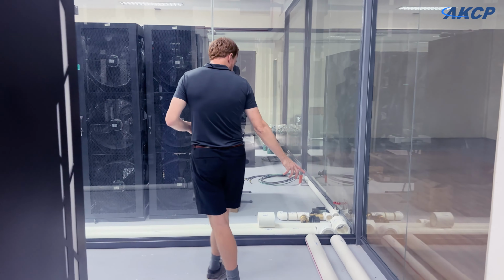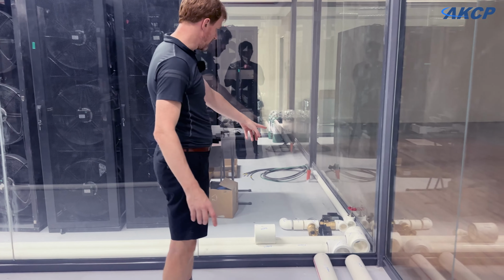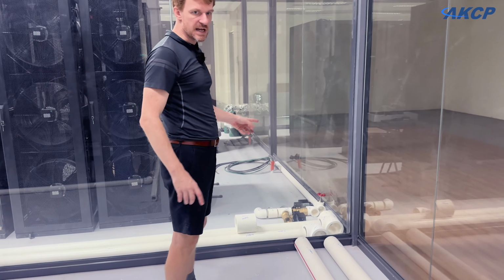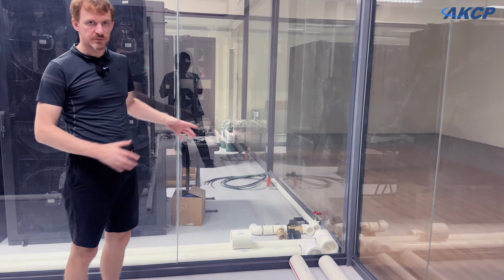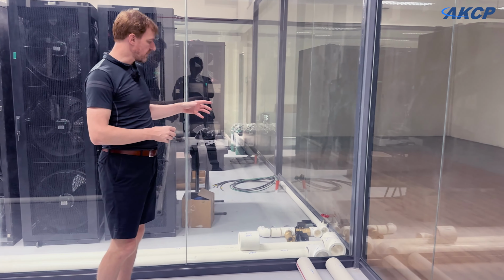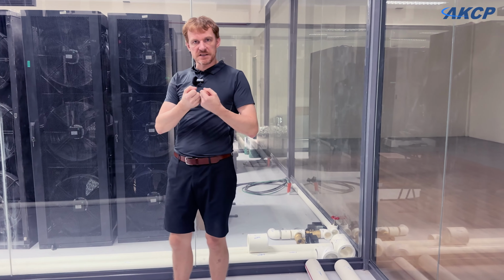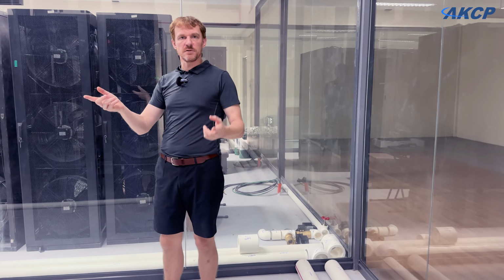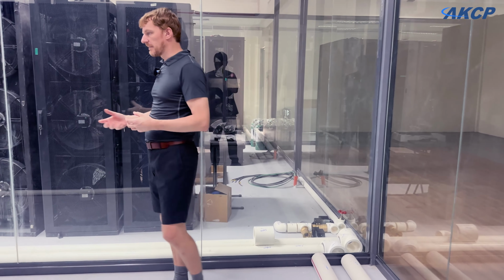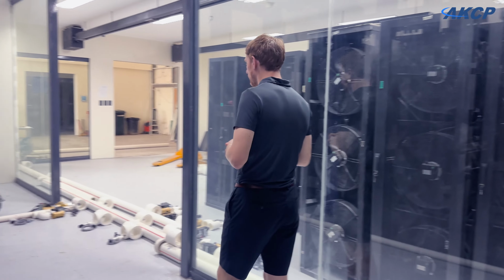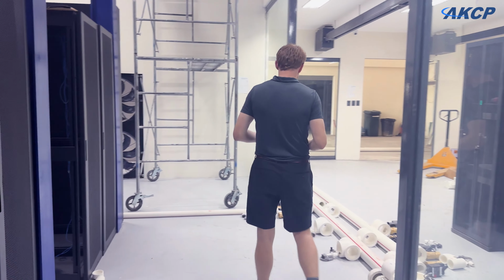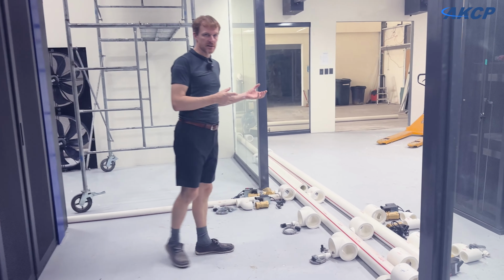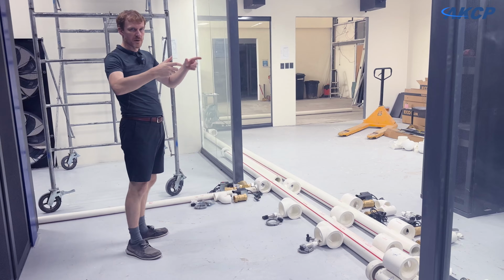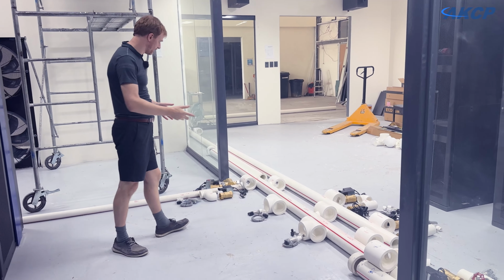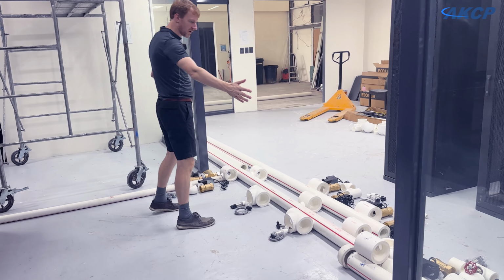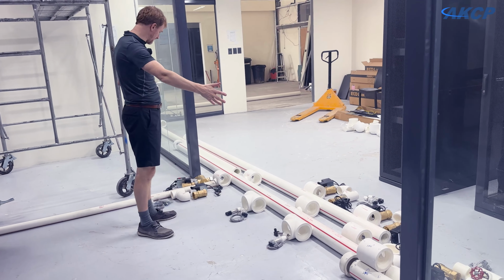Along the way, from the 4-inch main loop, we have 2-inch tap-offs which take the water out to the individual containment pods, and from those 2-inch tap-offs we split into 1-inch lines which go to the 2 AHUs inside each one. On the fan wall we'll also have connections, with a 2-inch line running in with 1-inch tap-offs going to each of the heat exchangers there. This is probably the most complex part of the water switching system, laid out on the floor.